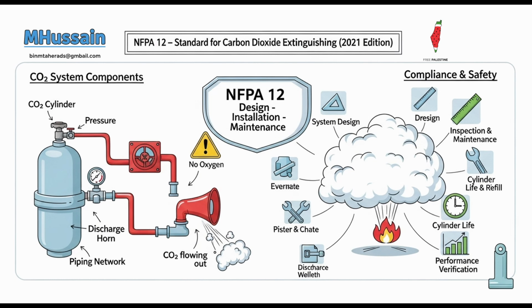Valves, controls. The operating devices themselves, including CO2 releasing devices, discharge controls, and equipment shutdown mechanisms, are all considered integral to the system's successful performance. They are designed to function reliably within a wide temperature range, typically from -20 degrees C (-4 degrees F) to 66 degrees C (150 degrees F). Wide temperature range. And must be protected from mechanical, chemical, or other damage. Crucially, any devices with manufacturer-specific connections used to control CO2 release must have distinctive or distinctively marked connections to prevent improper installation. Make sure you can't hook it up wrong. Because even a minor misconnection could lead to system failure.